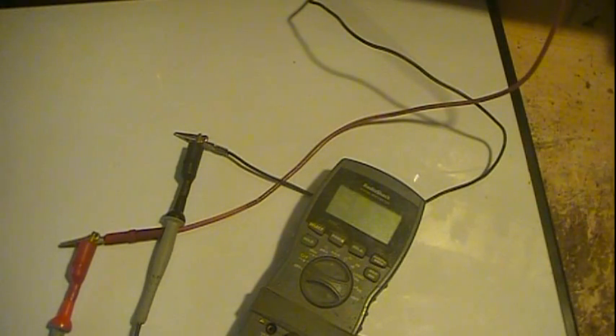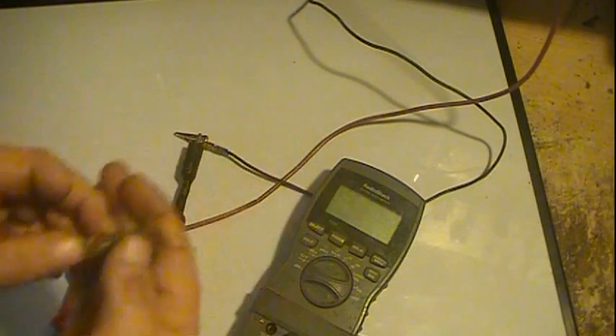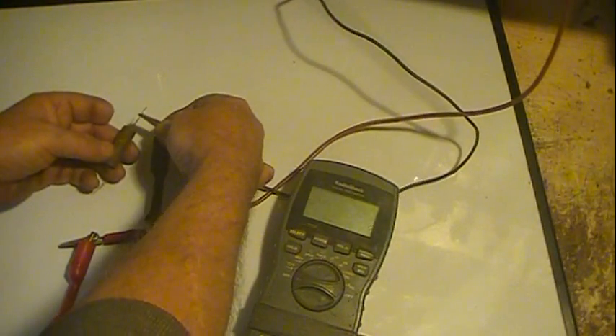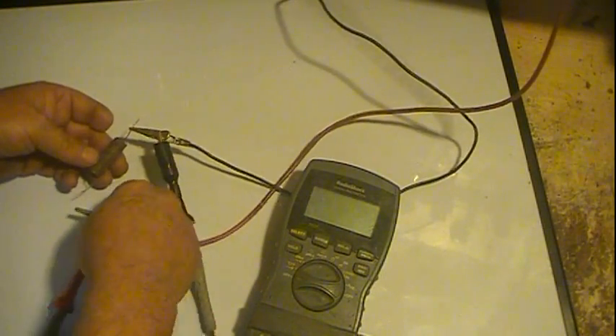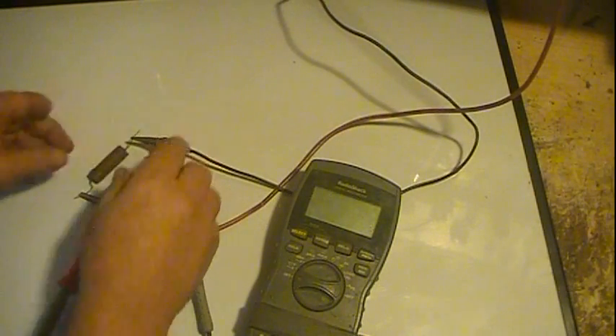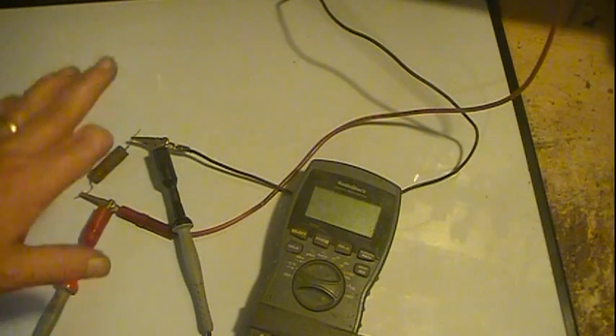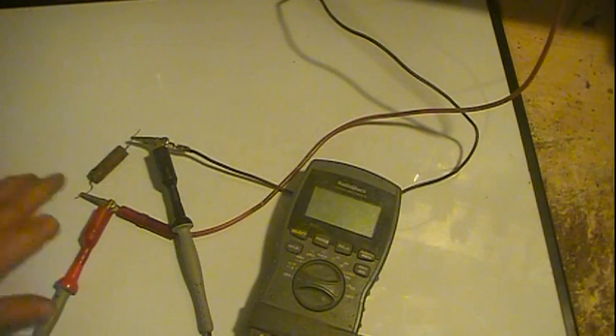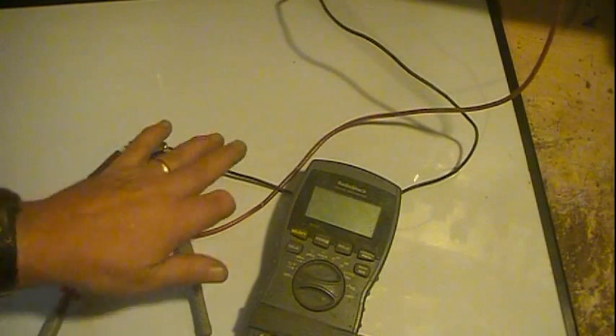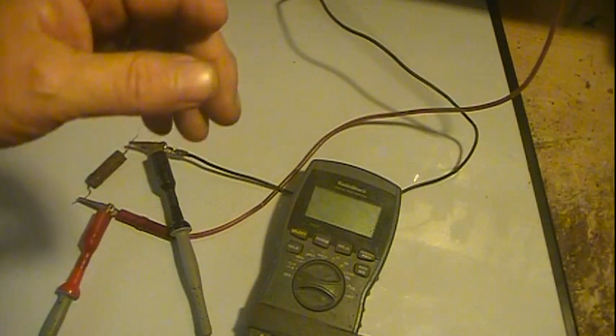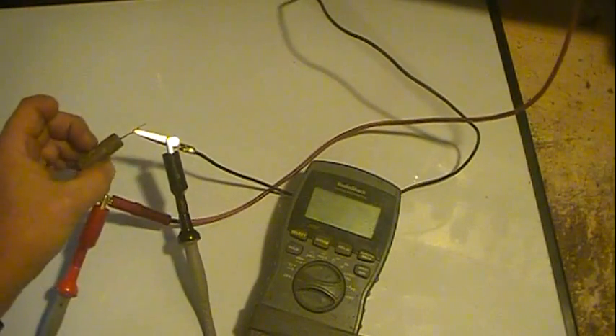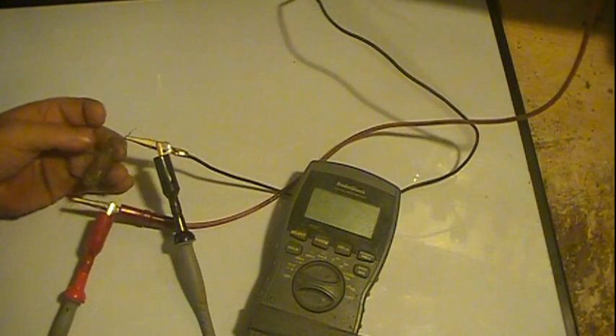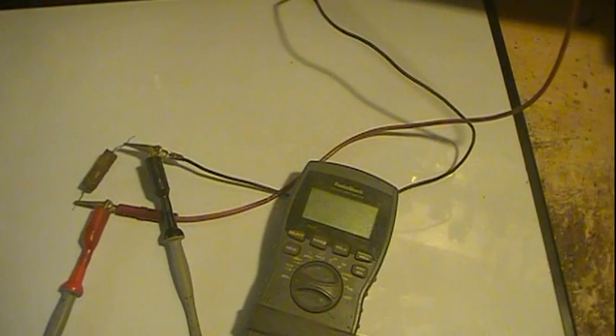But I have a 0.02 microfarad. I don't know if you can see that. It's kind of hard to see, and 600 volts. So we'll put that one on here. Now, paper caps are non-polarized, so you don't have to worry about which way you hook the leads up. If you're doing electrolytics, make sure you're hooking the positive lead to the positive, and these are black and red. Red for positive, black for negative. So you want to make sure you hook them up right, otherwise you might get a nasty surprise if you crank up the leakage really good. And see, that's a 0.02, like I said.